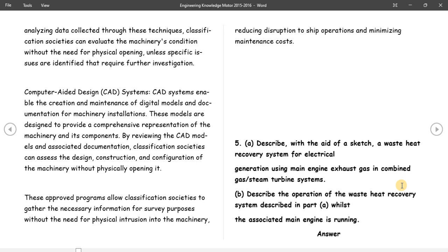The exhaust gas generated by the main engine is directed to the exhaust gas boiler. The flow of exhaust gas is controlled by dampers or valves. Next is the heat extraction. After the heat is extracted, we have the steam generation. The high temperature water absorbs heat from the exhaust gas and converts it into high pressure steam. Next is the steam expansion. The high pressure steam flows into the steam turbine where it expands and produces mechanical energy. This expansion of steam causes the turbine rotor to rotate.